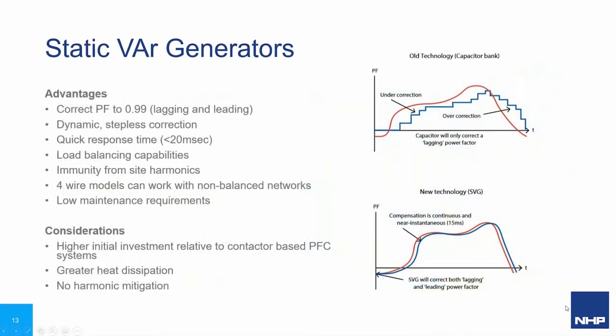So let's dive into the technology of static VAR generators a bit more. They have some pretty good advantages over capacitor bank PFC. They can correct to a power factor of 0.99 and above for both lagging and leading. They also provide dynamic stepless correction, and it's that quick response time of less than 20 milliseconds that really makes them stand out over capacitors. A lot of the time it can be minutes for a capacitor bank to get back to reacting to changes. They're also immune to site harmonics, and there are 4-wire models available that will work with non-balanced networks. Also, given the lack of moving components, the maintenance requirements are quite low, so service life is quite long.